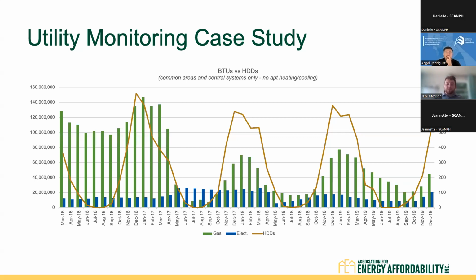However, as we got into April of 2018, you start to see the gas increase slightly and the electricity decrease slightly. It's very subtle. You see it in 2019 as well. This is an example of why alerts are important. If you don't have a knowledgeable person looking at this utility data, you're not going to really see that change. You're going to think it could be anything. But ultimately, it was the water heaters. In addition, it took two years for us to figure out that it was the water heaters, because we didn't have a BMS and didn't have monitoring of the system. We were able to catch it, but there was a significant time delay. Next slide, please.